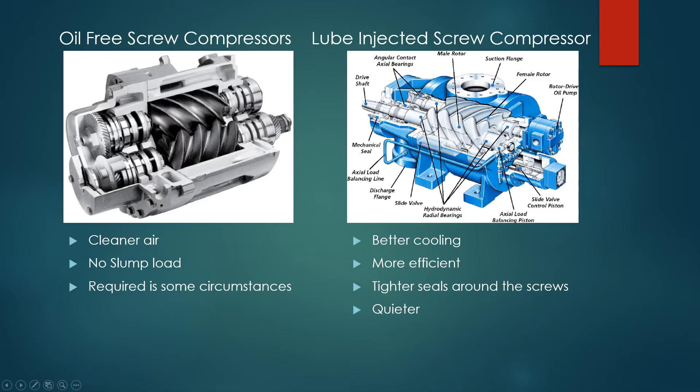There are two main types of screw compressors: oil-free screw compressors and lube-injected screw compressors. In lube-injected screw compressors, the oil offers cooling on the air as it is being compressed, which means the temperature of the compressed air is better controlled. Alternatively, in oil-free compressors, there is little to no cooling on the air and the temperature in the screw rises.